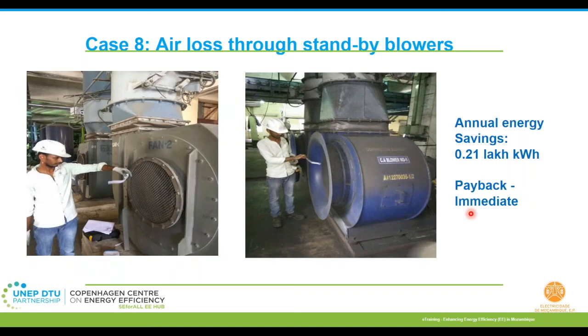Case 8 is about air loss through standby blowers. It's not just for blowers. You can also apply this for fans, different applications actually. So basically, there were high capacity blowers for fresh air intake in a large commercial complex building. This air would be passed further to filters and then introduced into the indoor air requirements for space conditioning. Generally you have two systems where one is always in operation and one is on standby mode. So here you have two blowers. One was operating and the other one was on standby.